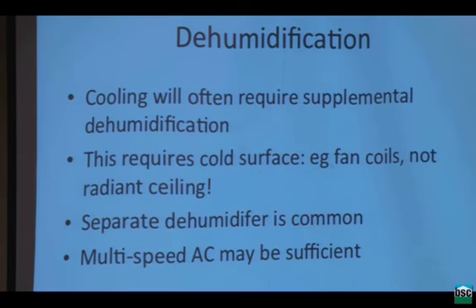Sorry, let me be clear. It's supposed to do none, and you don't want it to do any dehumidification because as soon as the water starts condensing, you're in serious trouble. So particularly with a radiantly cooled floor, you're going to need a separate ventilating dehumidification system, which is not an inexpensive system, and it's not easy to find. But you can do it, and for a very low load, zero energy office building, I do that in a heartbeat. Radiantly cooled ceilings, separate ventilating dehumidification system, you're great.